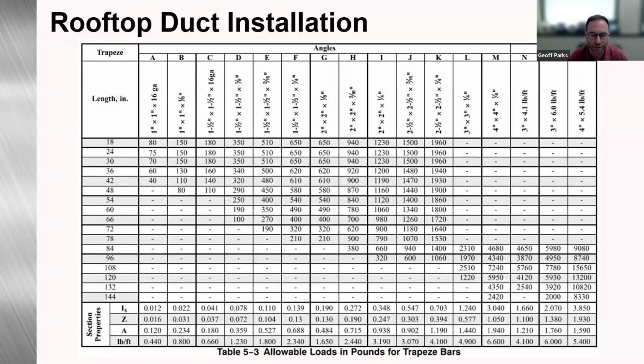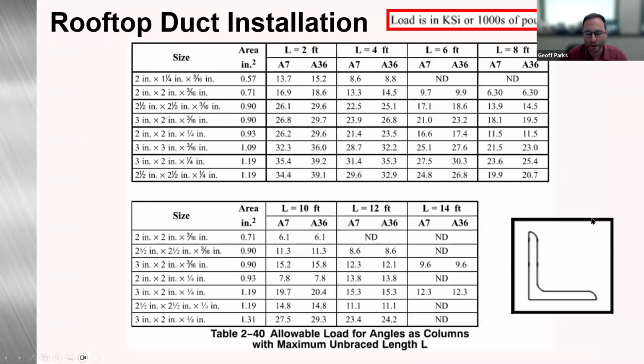So I'm throwing up table 5-3 here. So this is where you would size your trapeze based on the length of that trapeze and the load that it's going to see, based off the duct size, the duct weight, the spacings, and all that. And then here I'm showing table 2-40. This is the allowable load for angles as columns. So this is where you can size your support legs using angle.